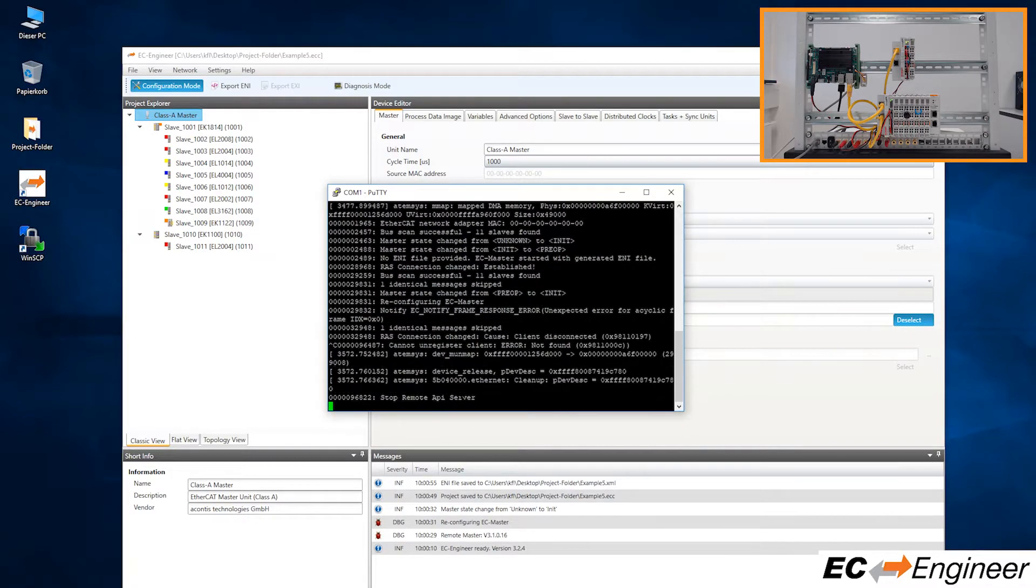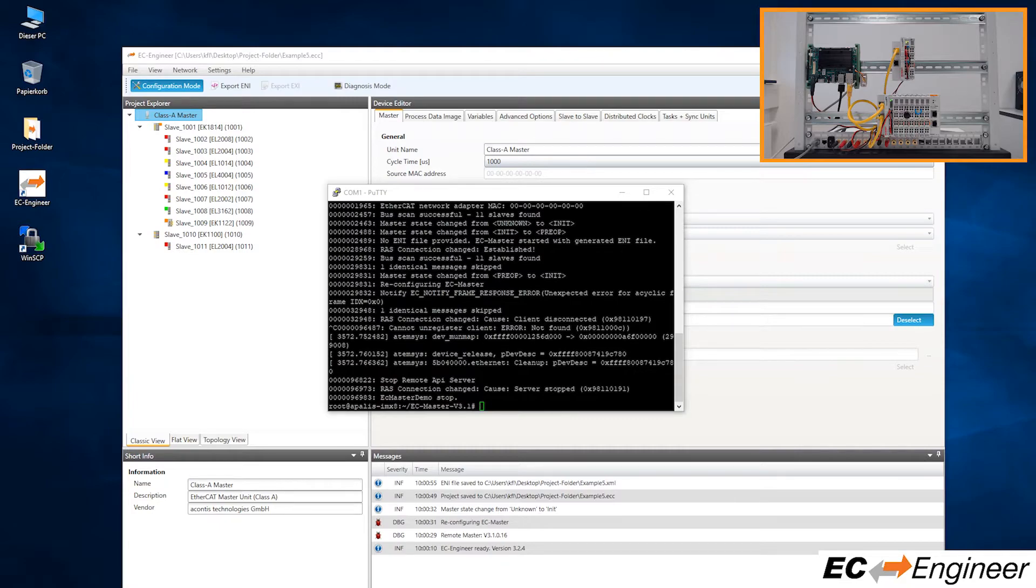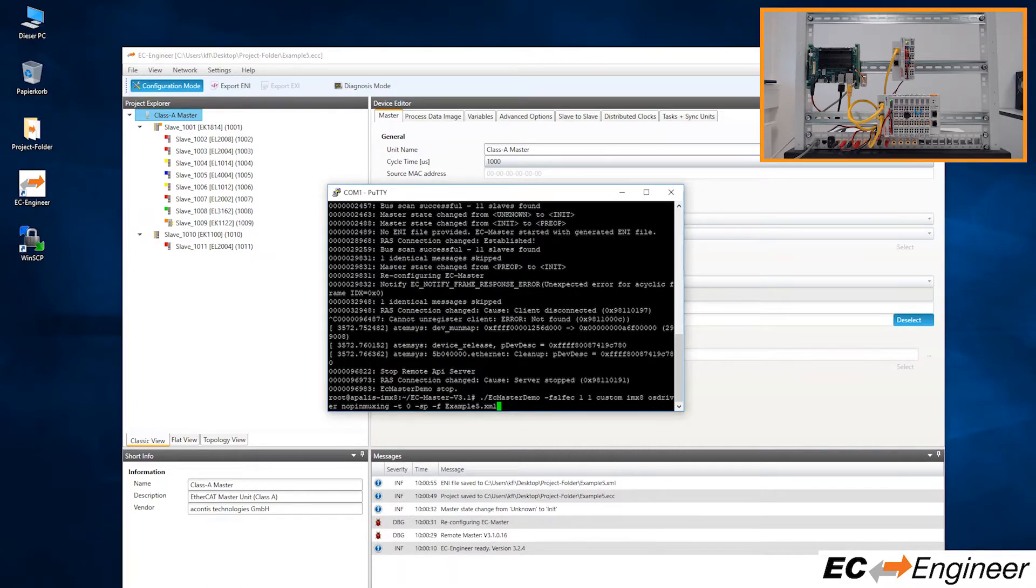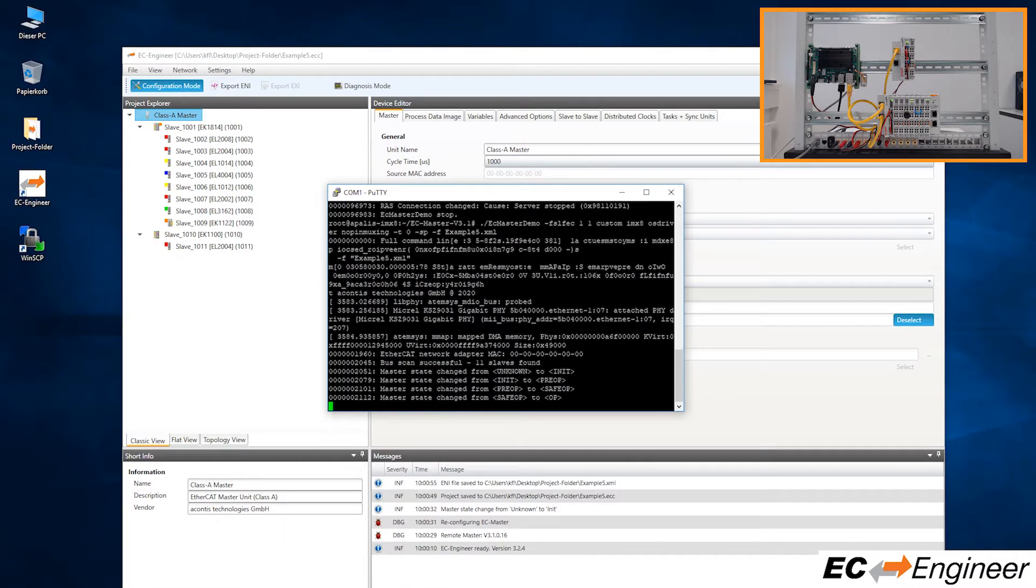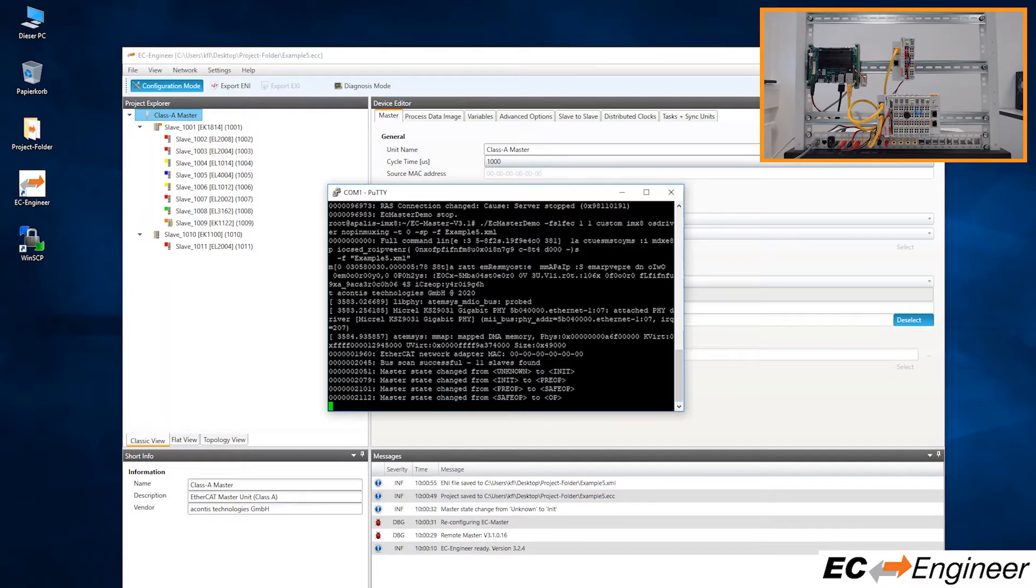With the ENI file now on the Linux system, stop the EC Master demo application and restart it, but this time also specifying to use the ENI file we just copied over. Notice that now the example application reports that it found the slave devices on the network and matched them to the configuration within the ENI file. So it will move through the EtherCAT state machine and set the devices into operational state.